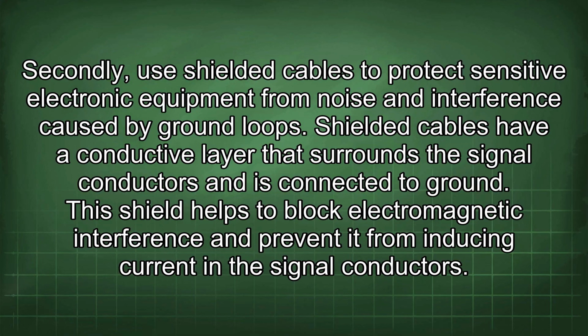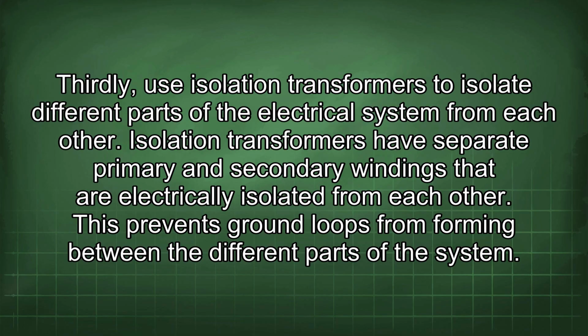Secondly, use shielded cables to protect sensitive electronic equipment from noise and interference caused by ground loops. Shielded cables have a conductive layer that surrounds the signal conductors and is connected to ground. This shield helps to block electromagnetic interference and prevent it from inducing current in the signal conductors. Thirdly, use isolation transformers to isolate different parts of the electrical system from each other. Isolation transformers have separate primary and secondary windings that are electrically isolated from each other. This prevents ground loops from forming between the different parts of the system.